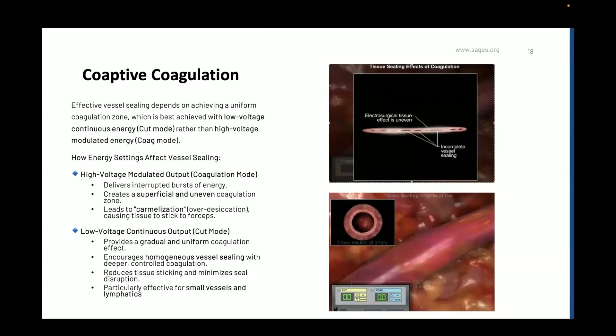So when you're using the coag mode, you remember you're delivering pulses of current in an uneven way, and this can lead to unevenly affected tissue and an incomplete seal. You could still seal the vessel, but it's not the most efficient or effective way. It can also lead to more caramelization of tissue, leading to the vessel sticking on your instrument, so that when you take it off, it can disrupt the coagulum that you've made.